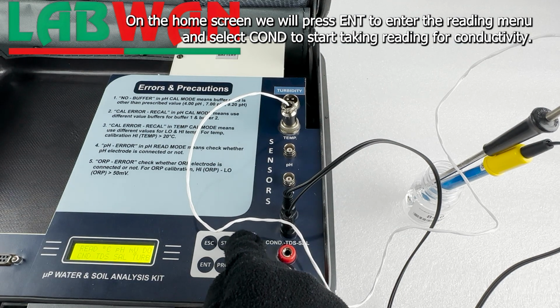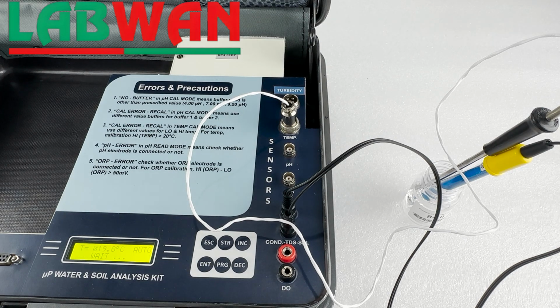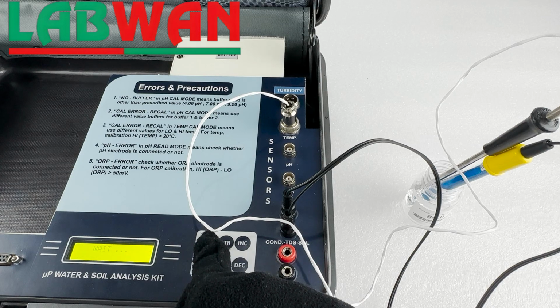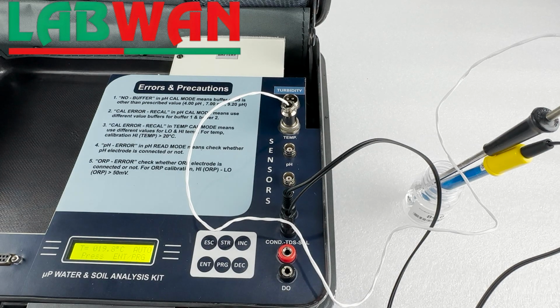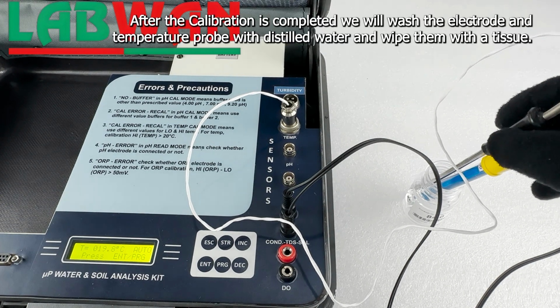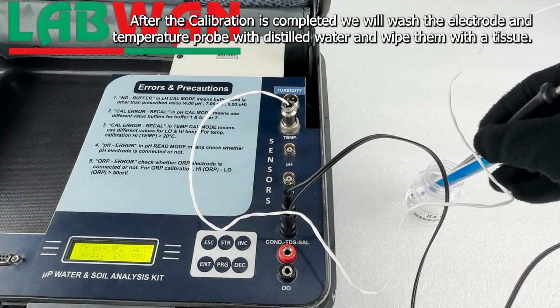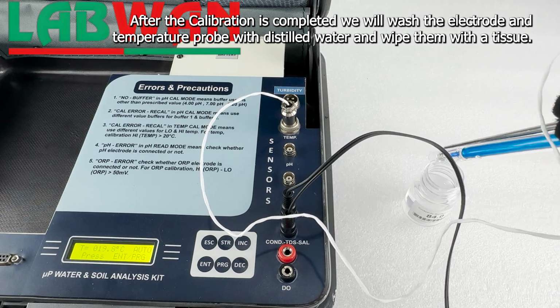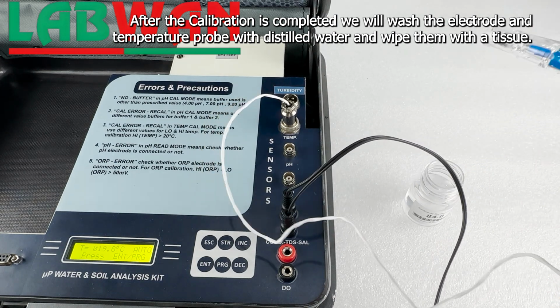On the home screen we will press ENT to enter the reading menu and select COND to start taking reading for conductivity. After the calibration is completed we will wash the electrode and temperature probe with distilled water and wipe them with a tissue.